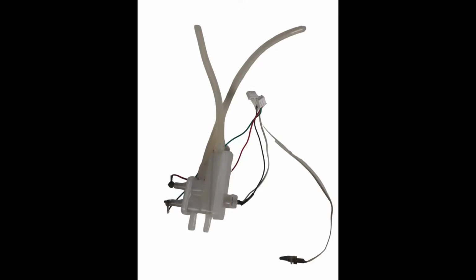Here's a photo of what this internal reservoir looks like when removed. On the right, you'll see the thermal probe, and on the left, those 2 probes are used to detect water level. As I said before, when continuity is detected across the 2, then it knows that the water level must be above the higher probe. The 2 hoses on the bottom of this both go to the external tank. 2 hoses are needed because the external tank is not ventilated, so one of them must allow air into the external tank. And the 2 hoses on the top, one goes to the pump and one goes to a vent, or acts as a vent.